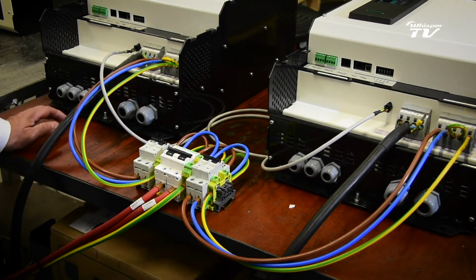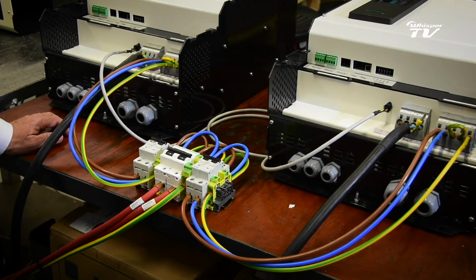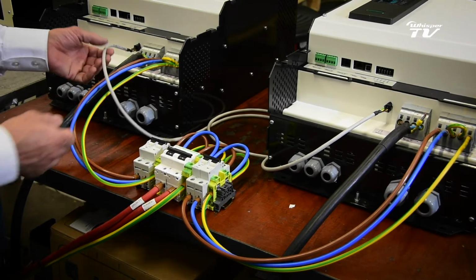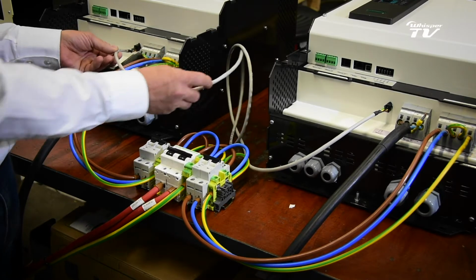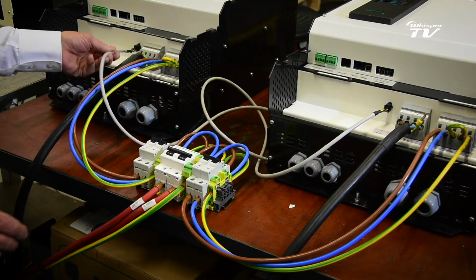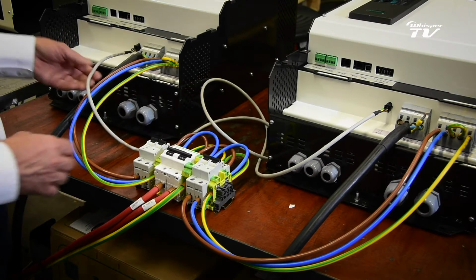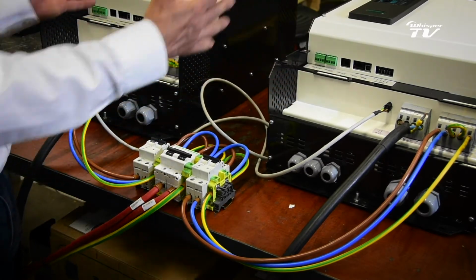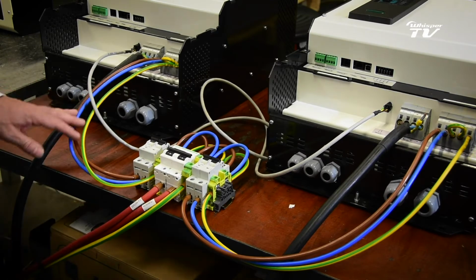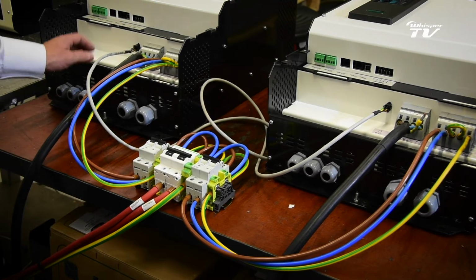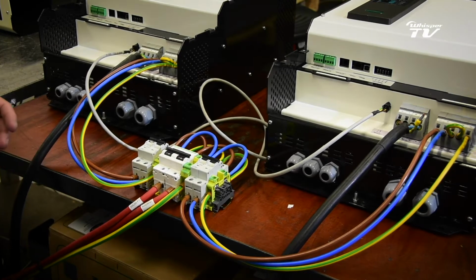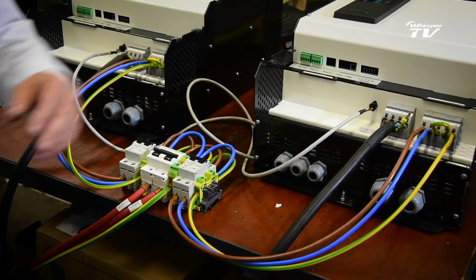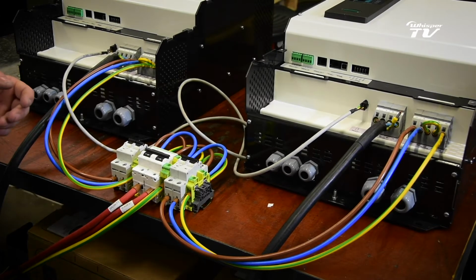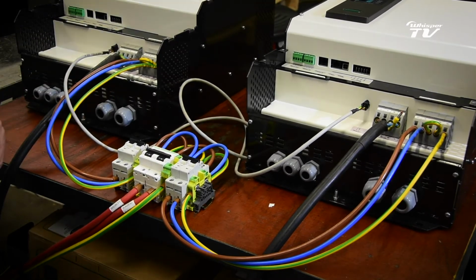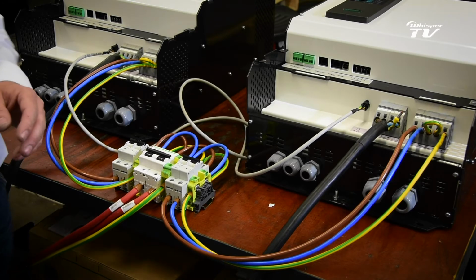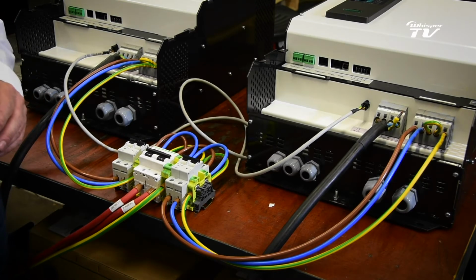There's one final connection in between the inverters, and that's a high-speed communication cable, which may not be that long, maximum 7 meters, but in most cases we want to have it shorter. It's also more practical to have it next to each other, so the cabling is also not that long. Then there's also some connectivity to WhisperPower bus, and we have some relay contacts for alarm and monitoring purposes. Then on the front we still have the on-off switch and the LED indications, which we will see later on.